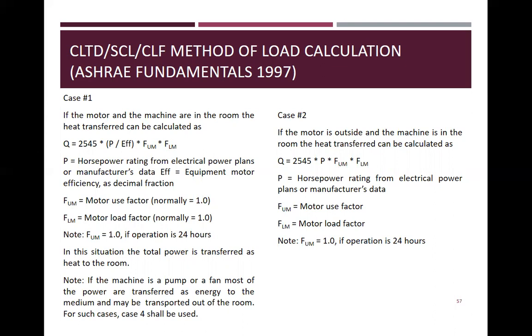FUM is the motor use factor, normally 1.0. FLM is the motor load factor, normally 1.0. Note FUM is 1.0 if operation is 24 hours. In this situation, the total power is transferred as heat to the room. Note again, if the machine is a pump or a fan, most of the power is transferred as energy to the medium and may be transported out of the room. For such cases, case 4 shall be used.